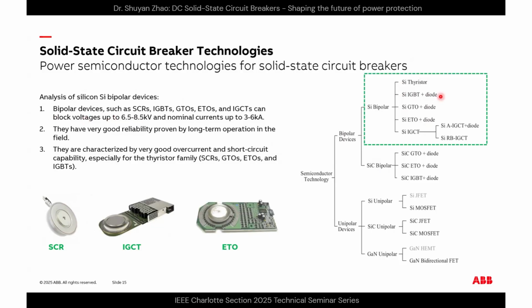Bipolar devices, such as thyristors or SCRs, IGBTs, gate turn-off thyristors (GTOs), ETOs, and IGCTs, can block voltage up to 6.5 to 8.5 kV. That's really high power actually, with a nominal current up to 3 to 6 kiloamps. Those devices are typically already being used in power systems because they require really high power ratings. So they have very good reliability proven by long-term operation in the field.